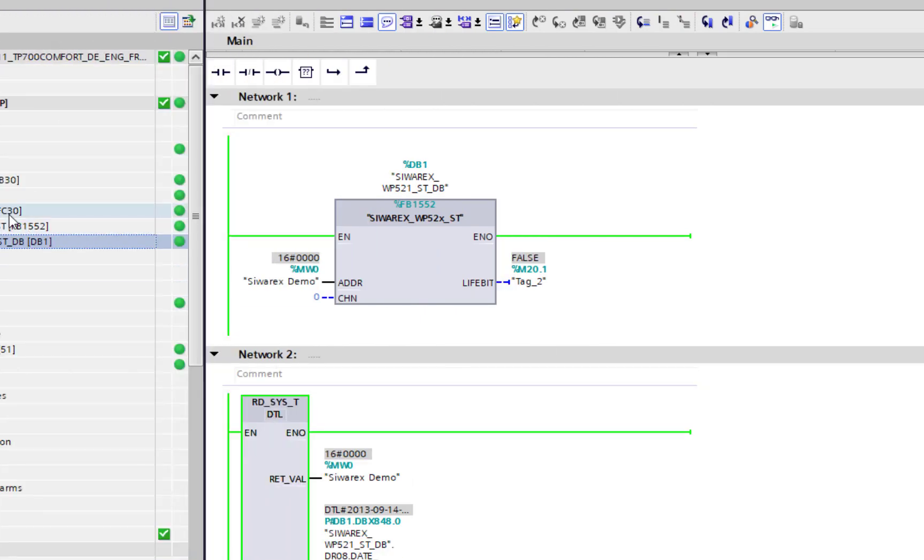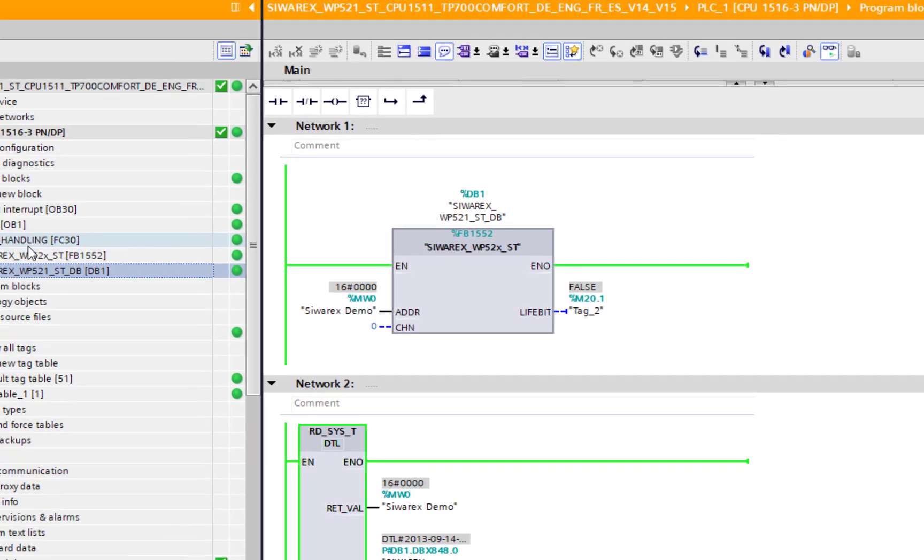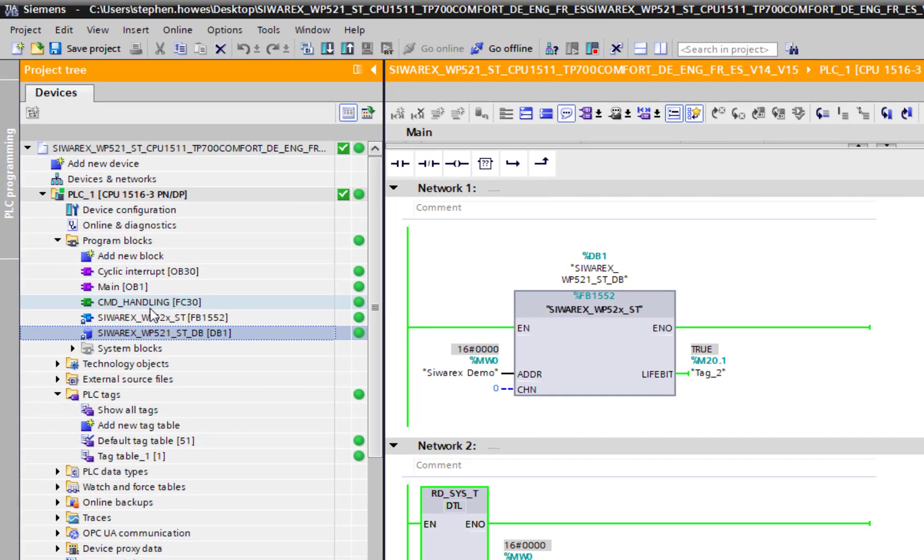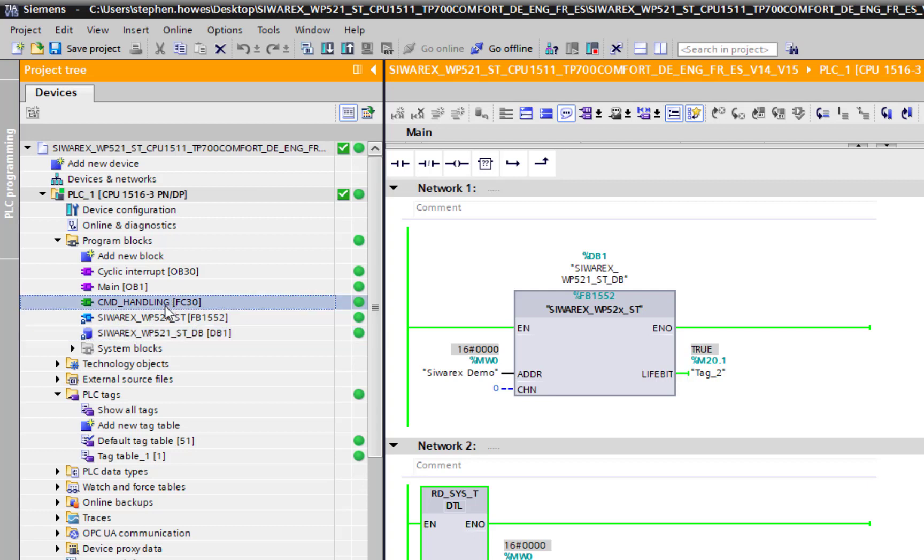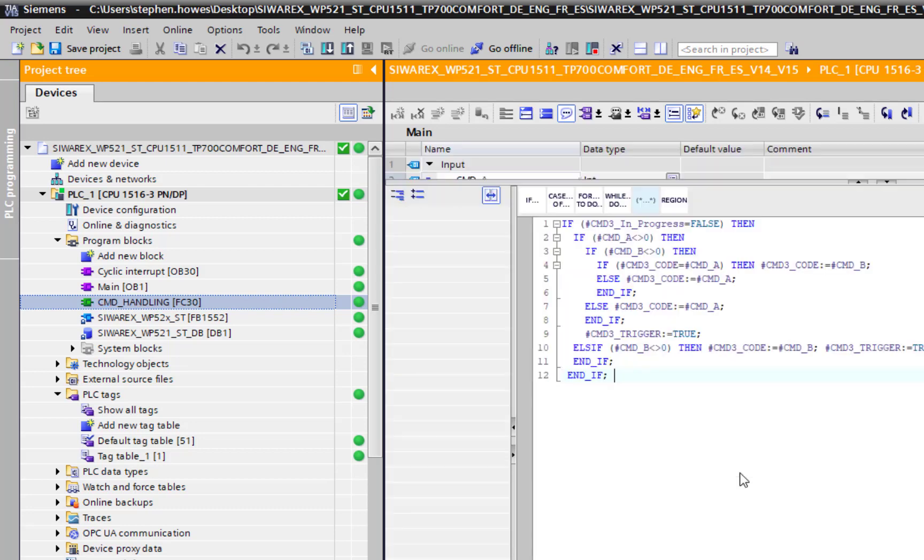As soon as I see this toggling on the life bit, that's it, I'm talking to the Siwarex. The way the Siwarex works, it works on commands being written to it. It's not constantly reading and writing all of the 500 parameters on there. It's just bringing back the process value and the diagnostics. That's two separate commands.